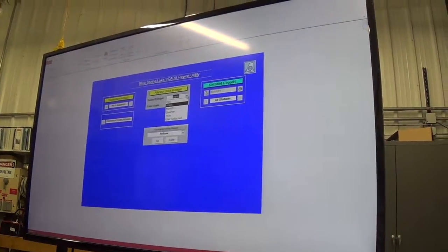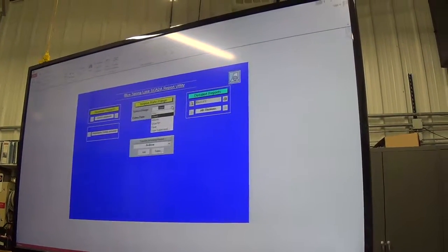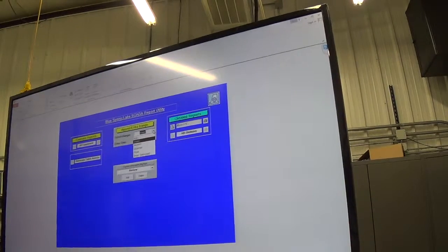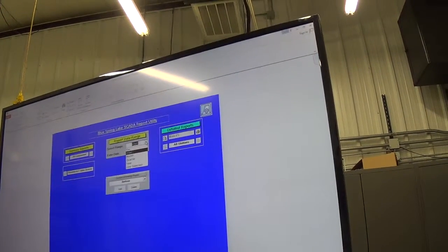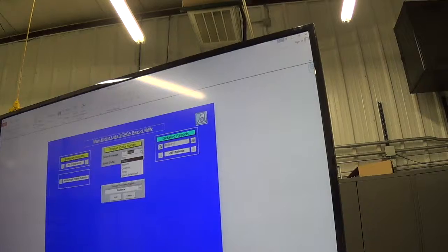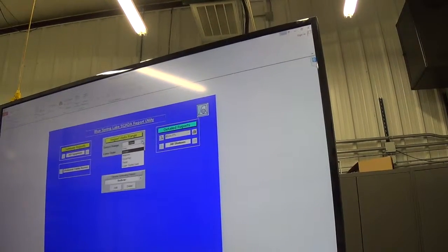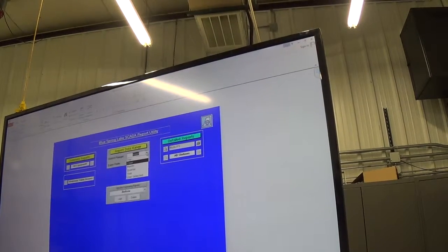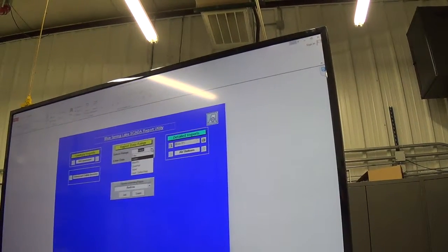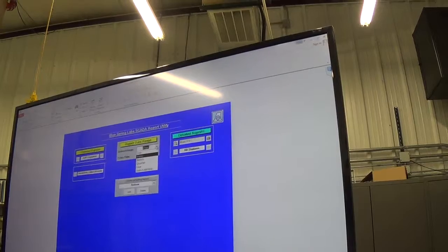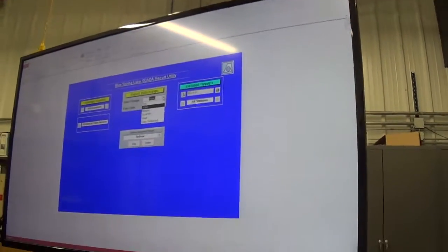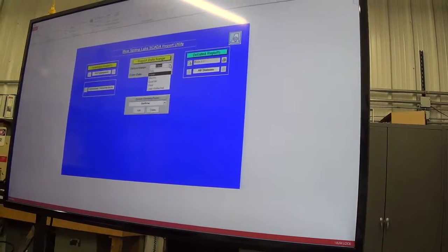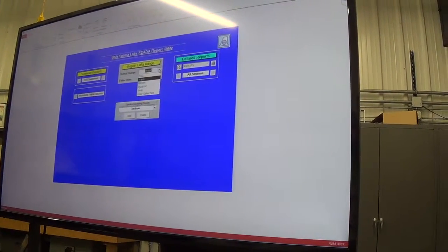I'm leery of putting it on the screen all the time, because it could differ, and the perception will be that one of these must be wrong. Well, they're not going to agree in the first place. One is calculated, one is actually derived from a value that the flow meter gives us directly from its internal. One is right and the other is calculated as a backup, but that's my only concern. You could show them both, as long as it's identified. As long as people know where it is in case there is a problem with that, we can do it. Is one more of an actual and one more of an average?